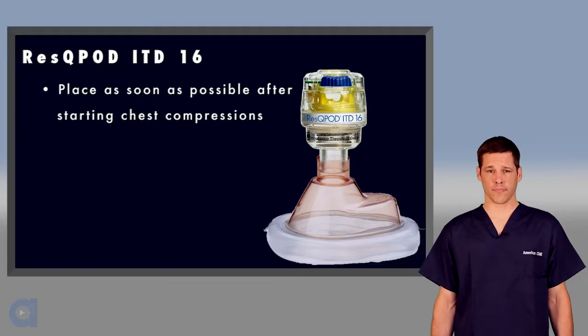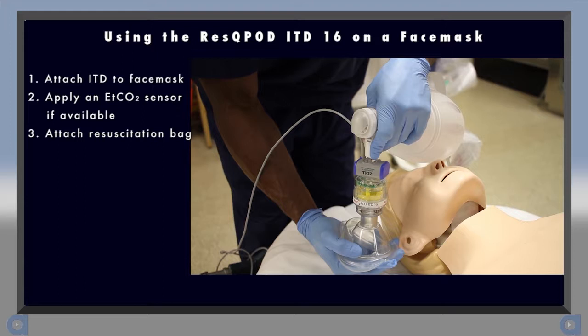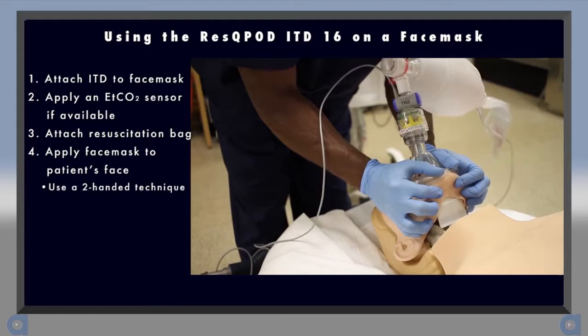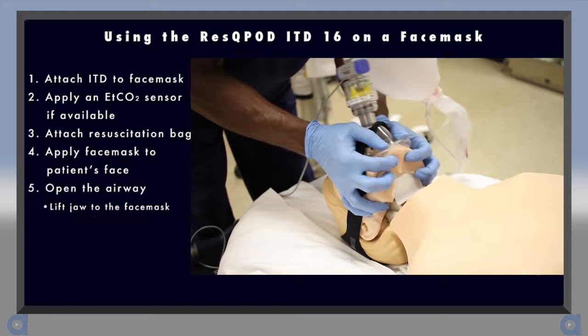Let's discuss how to use the ResQPOD ITD on a face mask. Begin by attaching the ResQPOD to the face mask. Next, apply an end-tidal CO2 sensor if available. Then, attach the ventilation source, such as a resuscitation bag, to the top of the circuit. Once the circuit is prepared, spread the cushion and position the mask over the patient's nose and mouth. Use a two-handed technique to ensure a good seal against the patient's face. A good face mask seal is critical for providing IPR therapy during BLS airway management. Using a head strap may help to maintain an airtight seal.